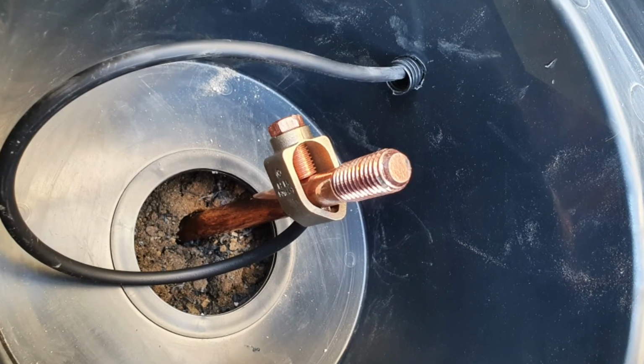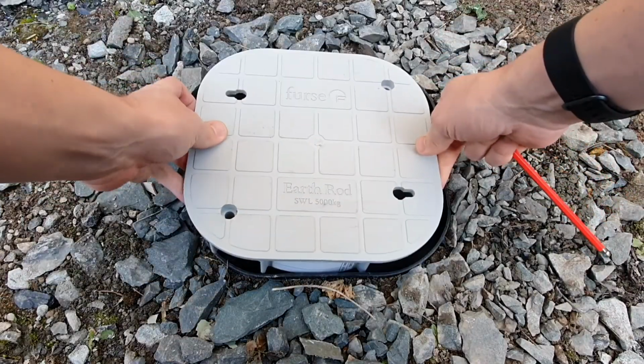Again, this shows how the Indra Smart Pro charger is a cut above the rest, as it actually will disconnect the charger at 30 volts instead of the maximum permissible 70 volts from BS 7671. This helps to mitigate the effects of this voltage rise on the reference earth under fault conditions. As you normally would with an earth rod, securely connect the cable to the clamp at the top of the rod and pop the termination into a suitable enclosure.